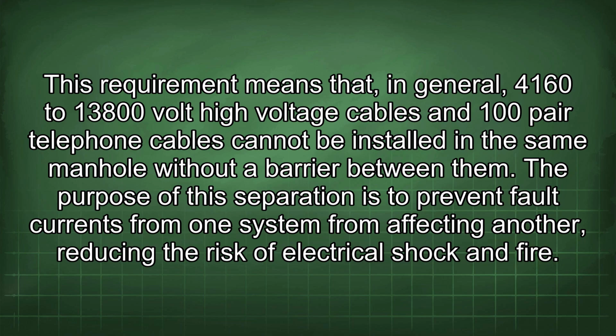4,160 to 13,800 volt high voltage cables and 100 pair telephone cables cannot be installed in the same manhole without a barrier between them. The purpose of this separation is to prevent fault currents from one system from affecting another, reducing the risk of electrical shock and fire.